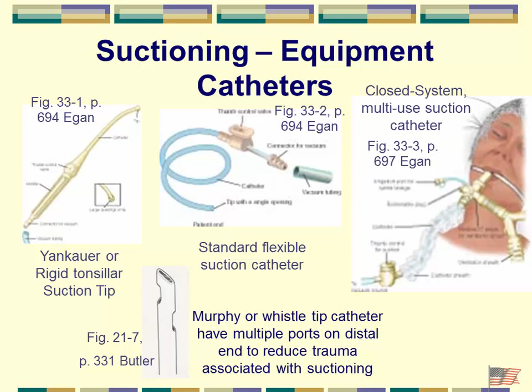port that is the primary port right here gets pulled up against the wall of, or is pushing up against the wall of the airway, you don't want there to not have any suction there. That'll cause some trauma to that area. So we're going to have alternate areas that the vacuum can still pull through without necessarily pulling against the mucosa of the tracheal wall.